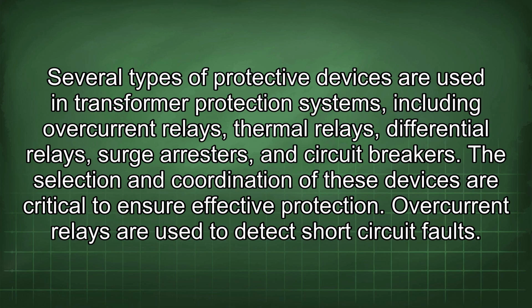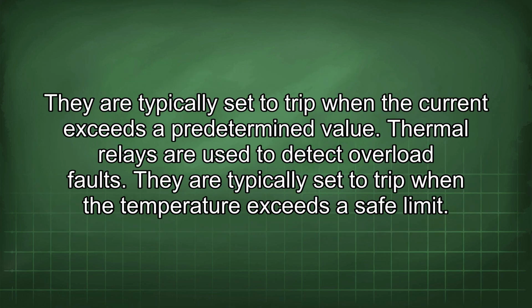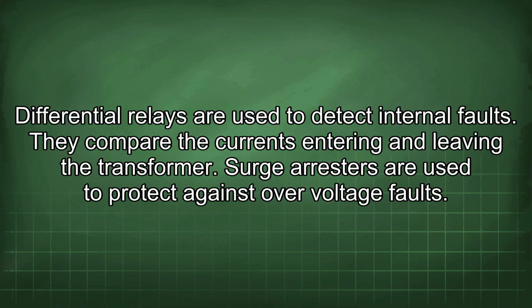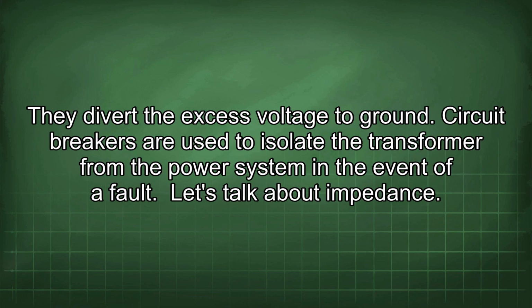Overcurrent relays are used to detect short-circuit faults. They are typically set to trip when the current exceeds a predetermined value. Thermal relays are used to detect overload faults. They are typically set to trip when the temperature exceeds a safe limit. Differential relays are used to detect internal faults. They compare the currents entering and leaving the transformer. Surge arresters are used to protect against overvoltage faults. They divert the excess voltage to ground. Circuit breakers are used to isolate the transformer from the power system in the event of a fault.